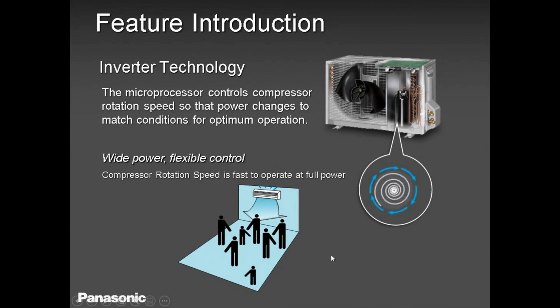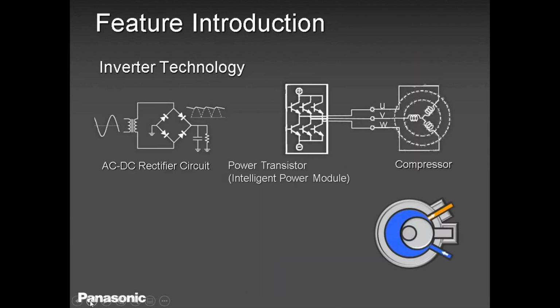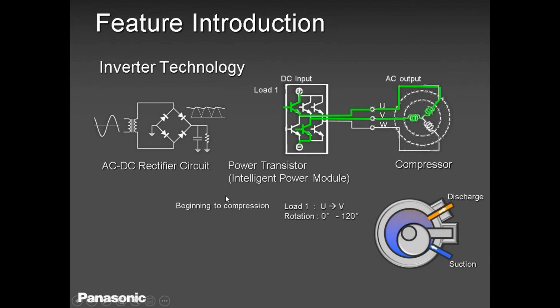If the sensors are telling the compressor there's not much load, then the compressor will run very slowly. Okay, this is a very simple way of explaining how a microprocessor compressor works, or how inverter technology operates. When there's less load, the load is you. When there's less load, the intake sensor senses not much heat in terms of cooling, so the compressor will go slow.